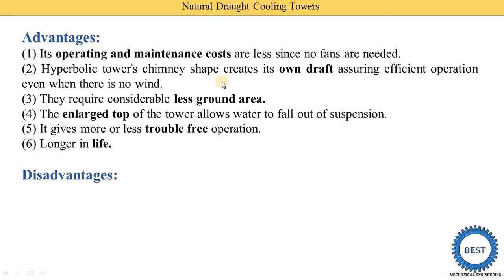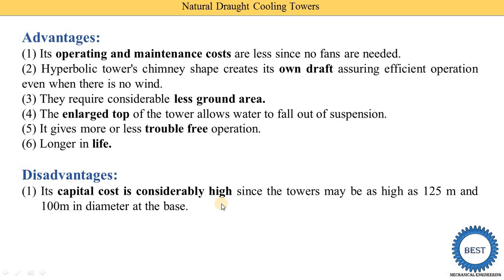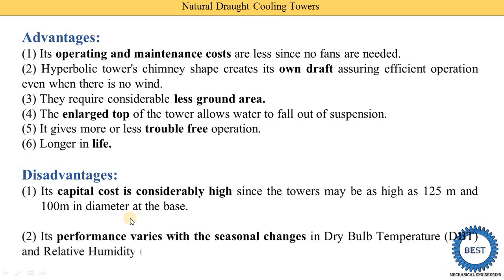There are also disadvantages. First, capital cost is considerably high since the tower may be as high as 125 meters with a base diameter of 100 meters, and they are constructed from concrete — so initial cost is very high. Second, its performance varies with seasonal change; performance depends on the dry-bulb temperature and relative humidity of the air, so as seasons change, dry-bulb temperature and relative humidity change, and performance varies.